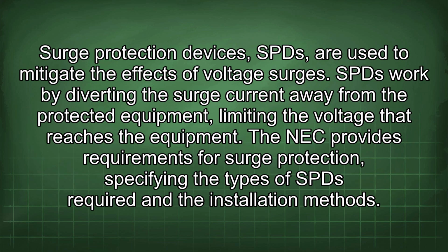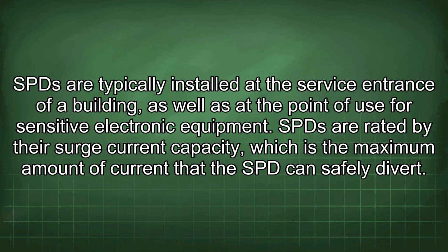Surge protection devices, SPDs, are used to mitigate the effects of voltage surges. SPDs work by diverting the surge current away from the protected equipment, limiting the voltage that reaches the equipment. The NEC provides requirements for surge protection, specifying the types of SPD required and the installation methods.